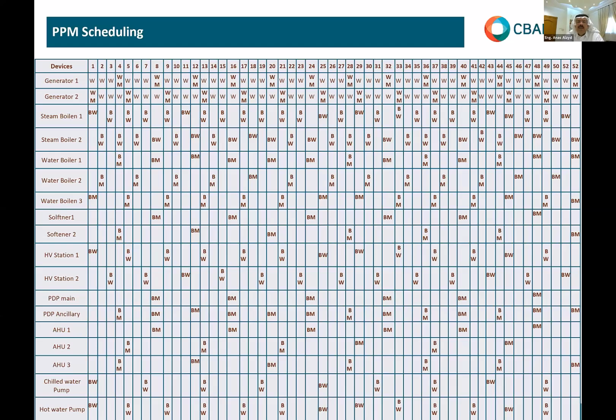Then I go back and see what's the requirement for doing a PPM maintenance on it. I have to go and read the manual. Now, if you have a contract with the landlord or with an outside company, you need to sit down with them and ask what's the requirement, for example, to do a PPM on the autoclave, or the examination light, or even the cylinders. What's the PPM requirement for it? It doesn't need 5 years maintenance, it needs monthly maintenance, depends on the equipment. So you put the equipment on one side, and then in the year, we have 52 weeks.